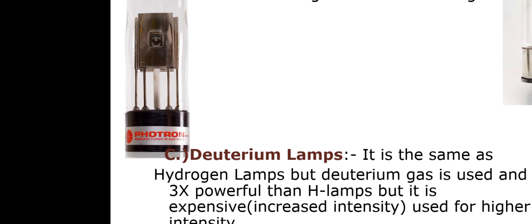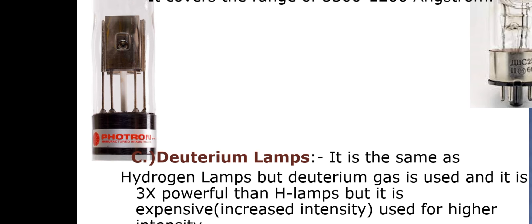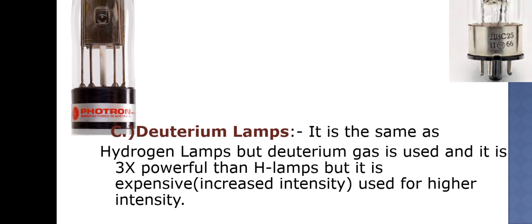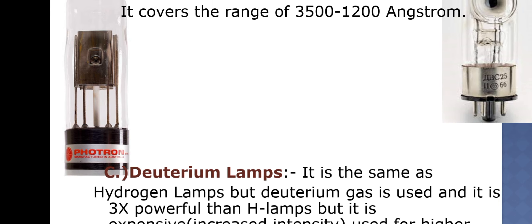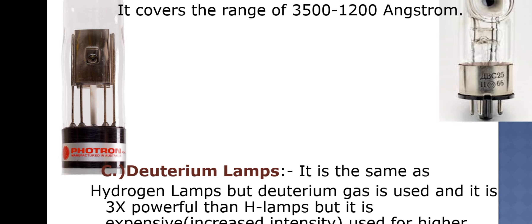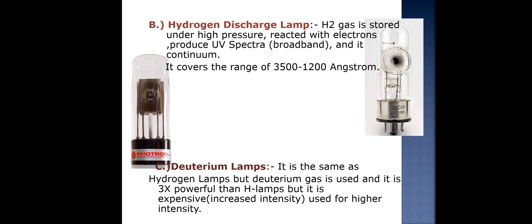The deuterium lamp is similar in type to the hydrogen lamp, but deuterium gas is used instead. It is 3 times more powerful than the hydrogen lamp and is also more expensive. It produces increased intensity of UV radiation and is used for higher radiation studies.